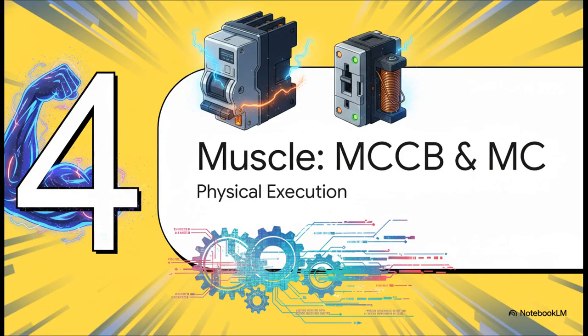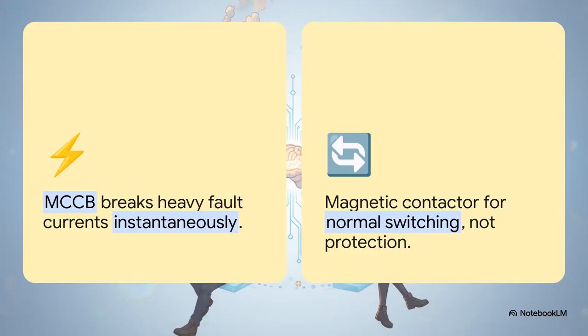Next up, Section 4, the muscle, the MCCB and contactors. If the SMCD is the brain doing all the heavy thinking, we need to look at the muscle that physically executes its commands. And there's a really brilliant division of labor going on here. For your daily non-fault switching, like scheduled load management, you rely on the magnetic contactor. It's an industrial-grade switch mechanically interlocked to prevent it from rapidly flipping on and off, which causes a highly damaging effect we call chattering. But here's the kicker.